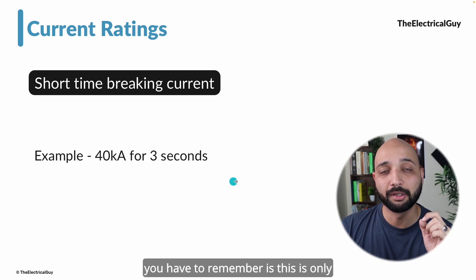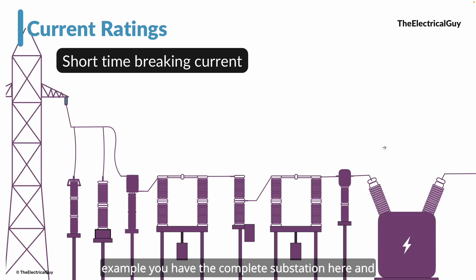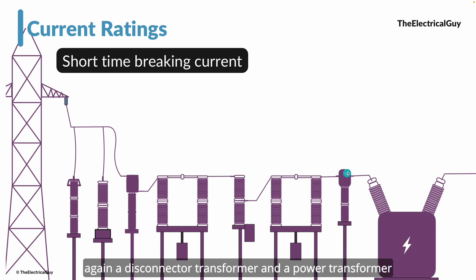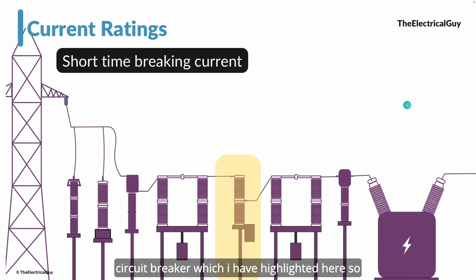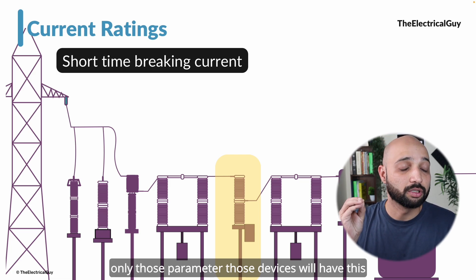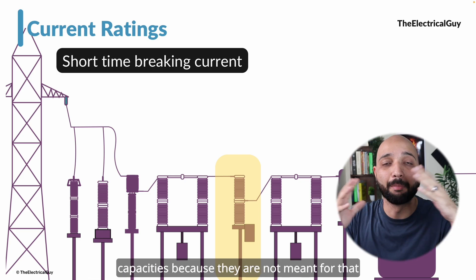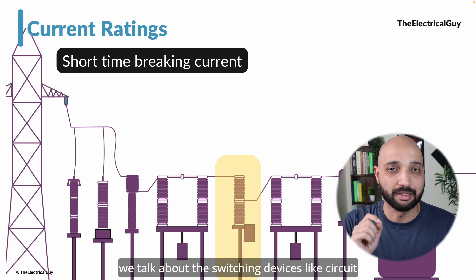This is only limited to switching devices and not all switchgear. In a complete substation you may have lightning arrestors, capacitor voltage transformers, current transformers, disconnectors, circuit breakers, and power transformers. Not all devices will have the short time breaking current capacity — only the circuit breaker. Devices like current transformers will not have short time breaking capacity because they are not meant for that. So the short time breaking current capacity is very important specifically for switching devices like circuit breakers.